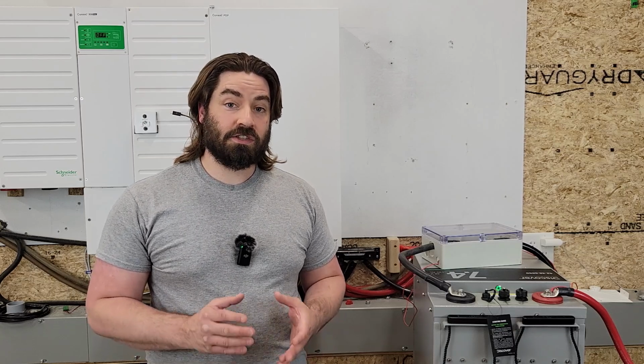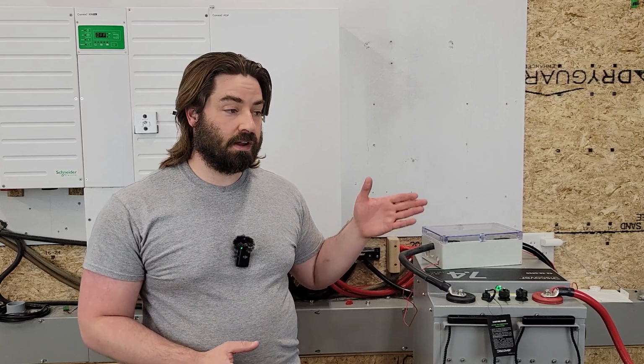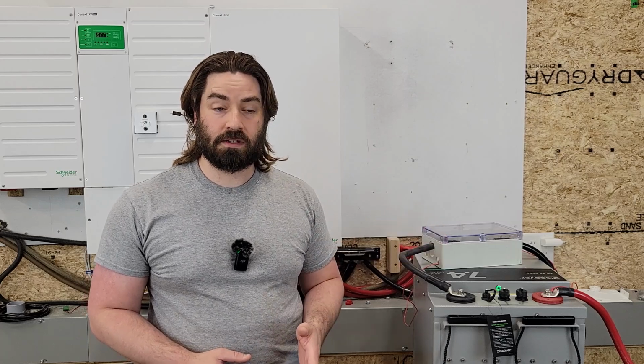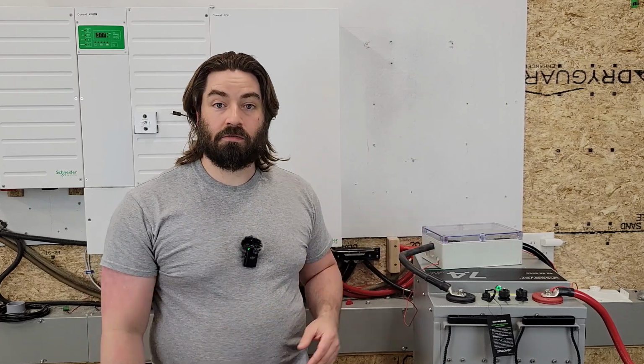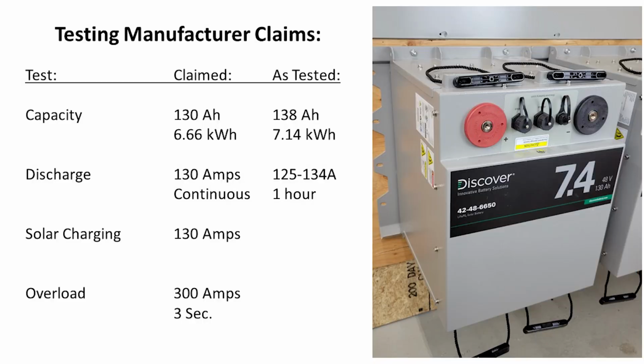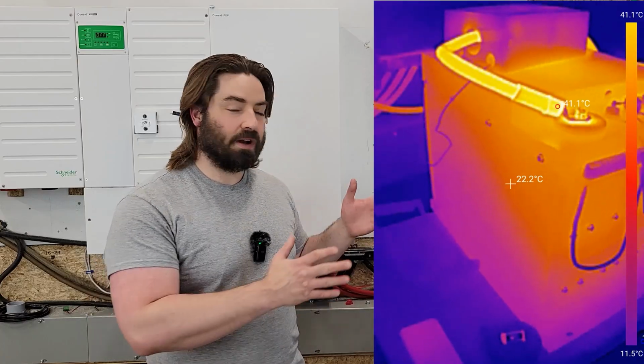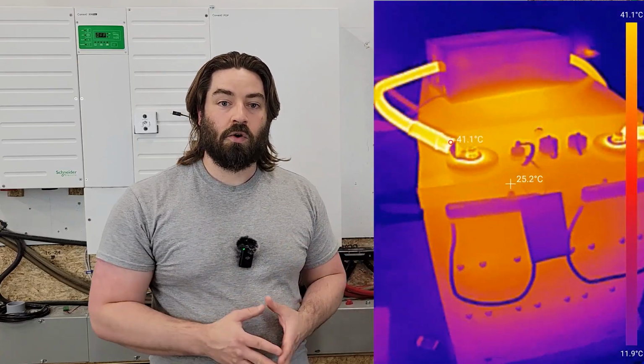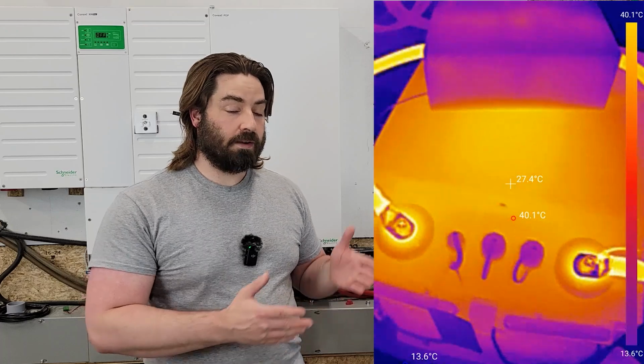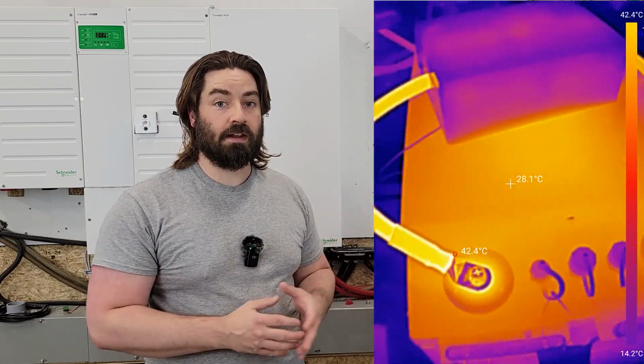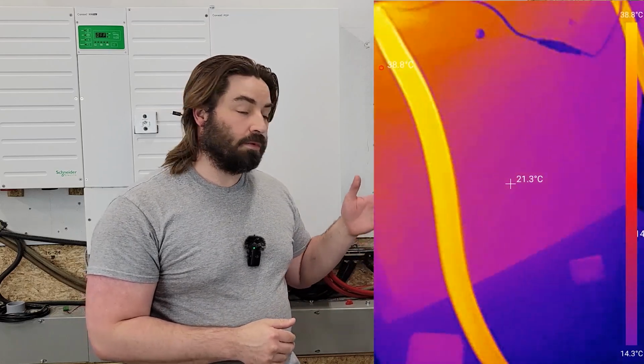The specifications written in the manual say that it can run 130 amps continuous. Well, we ran it for an hour and it ran 130 amps. Yes, we were between 126 and 134 amps during the majority of the test, but it never shut off due to overheating or something like that. And I have had equipment in the past that cannot hit its own specification. So whenever the piece of equipment can hit its own specification, that is a big plus in my book. I'm glad that it did that.